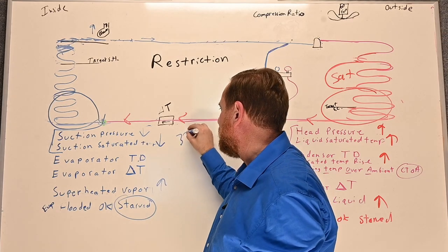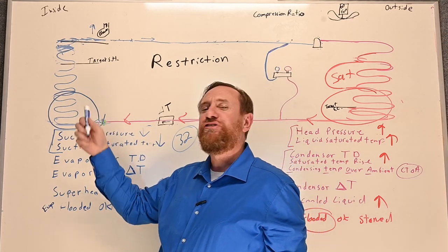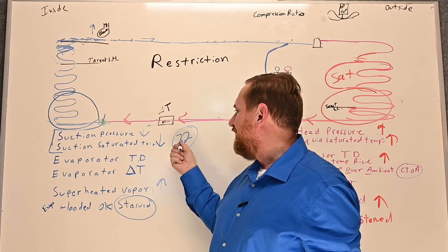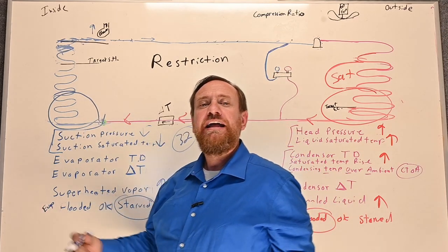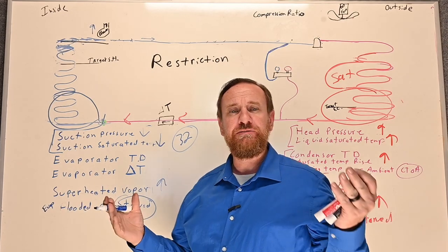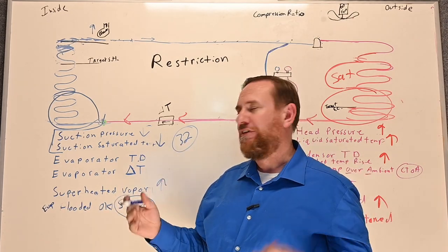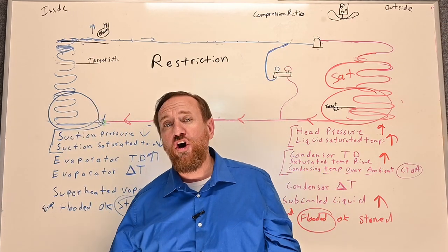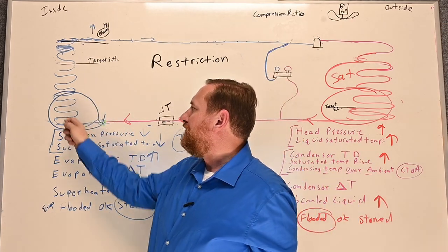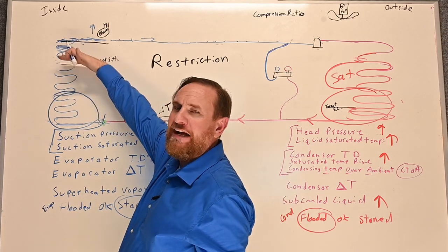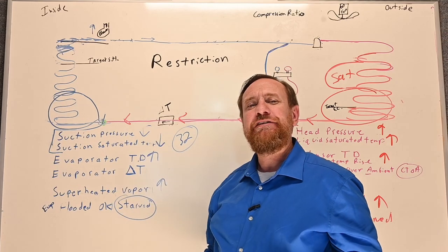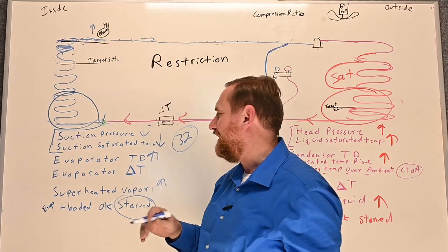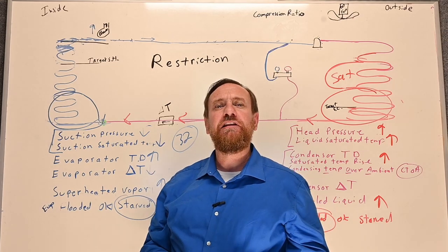If the saturated temperature drops below 32°F, the evaporator coil starts to freeze, beginning from the metering device moving forward. Also, because the saturated temperature drops lower, it's much farther from the return air temperature, so the evaporator TD is much farther apart — the refrigerant boiling temperature is much lower than the air temperature. Because we're boiling refrigerant in a much smaller area rather than the whole coil, we're absorbing less heat overall, so the delta T of the air — temperature in versus temperature out — will drop.